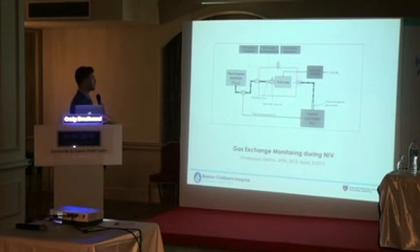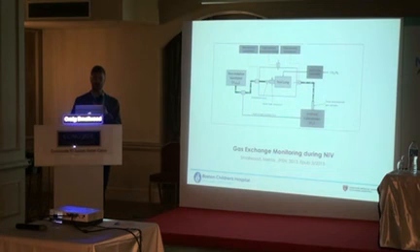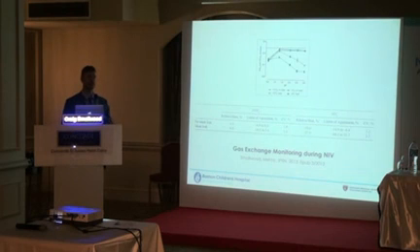I used the same kind of calibration system that we did. So you can pretty much ignore everything outside this box, but imagine this was the patient inside here. We'd put a canopy on top of the patient who's breathing with a mask or nasal prongs. And then similarly to the canopy device for spontaneously breathing children on no support, we would then aspirate the gas flow coming out of there, measure the gas concentrations, and estimate energy expenditure. The important feature that we found was that we had to closely match the pump flow, the amount of gas that we're aspirating out of that chamber, to match the patient's total inspired gas.